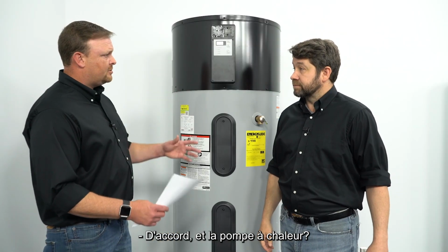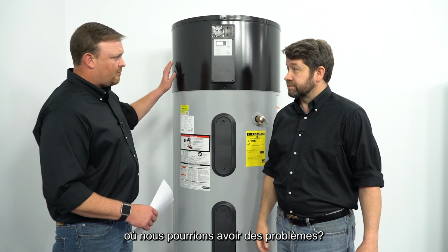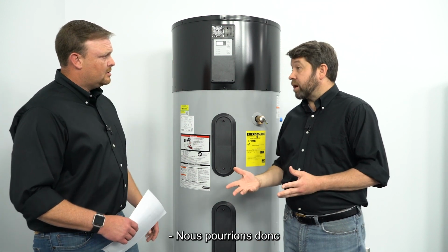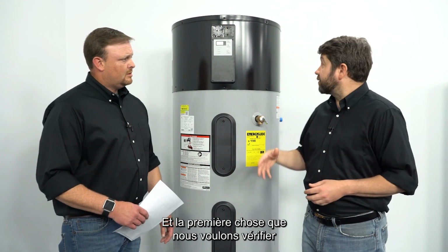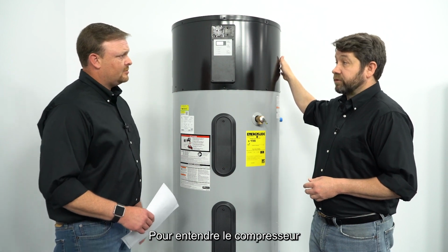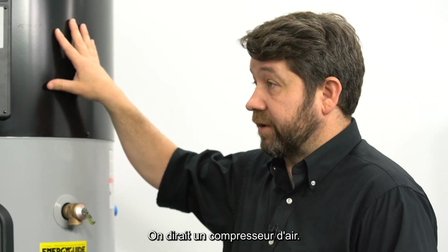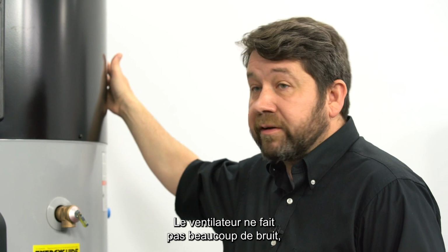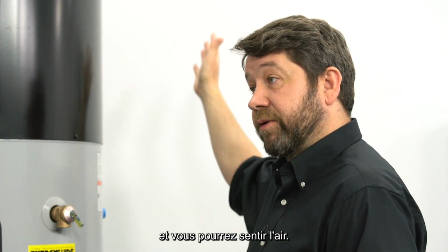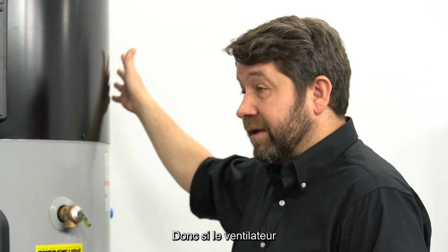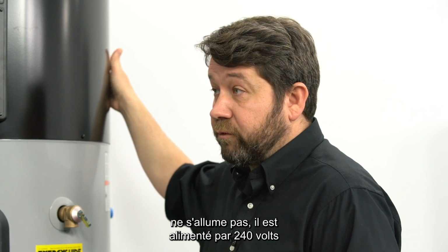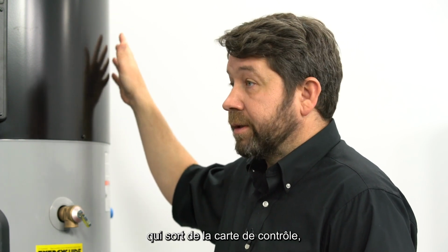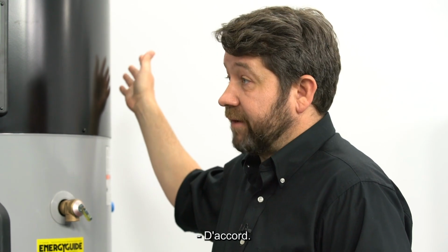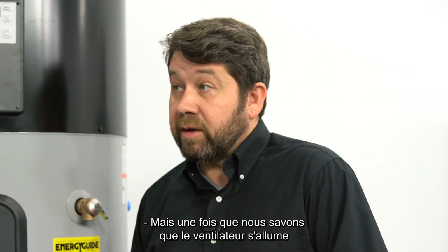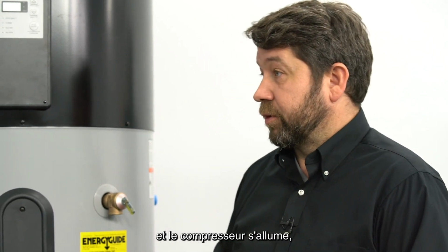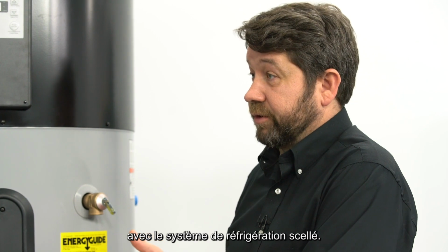Okay, what about the heat pump? Are there any situations where we might have problems with the heat pump? So we could have some problems with the heat pump, and the first thing that we want to check is to make sure that the fan is coming on. You can hear the compressor come on, and it sounds kind of like an air compressor. The fan doesn't make much noise, but you'll be able to see it and feel the air. If the fan's not coming on, it is powered by 240 volts that comes off the control board. It may just be a loose connection, or it could be a bad fan. But once we know the fan is coming on and the compressor is coming on, we could have a problem with the sealed refrigeration system.